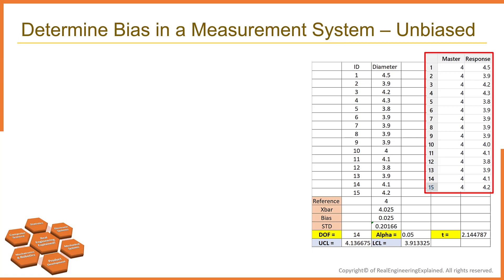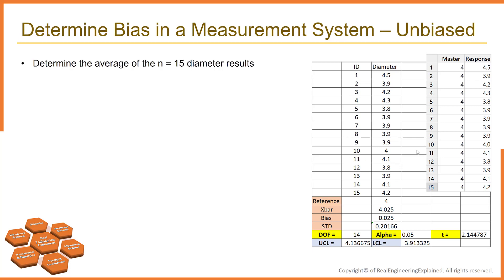To further confirm that there is no bias present, the engineer needs to construct a 95 percent confidence interval around the average diameter. If the confidence interval includes 4 millimeters — our reference value — the engineer can assume there is no evidence of bias being present.